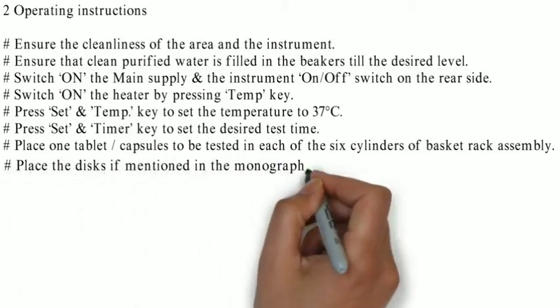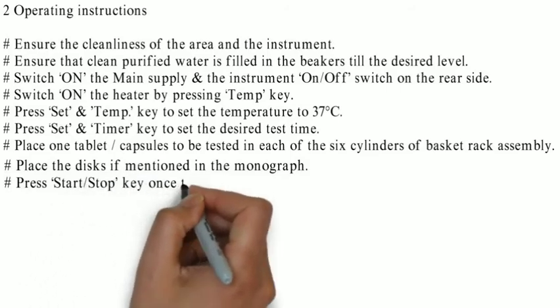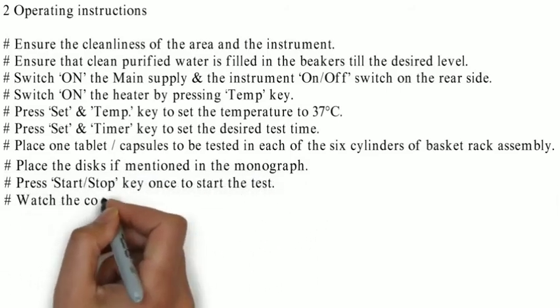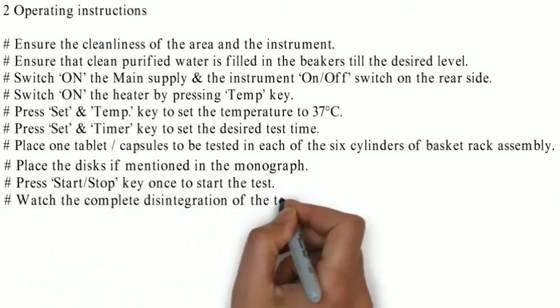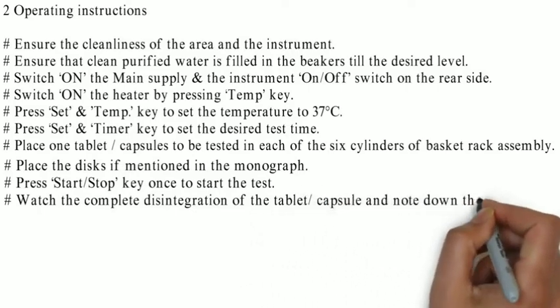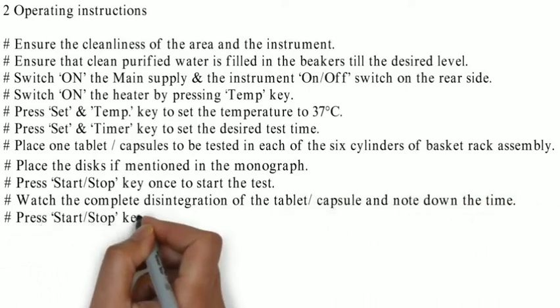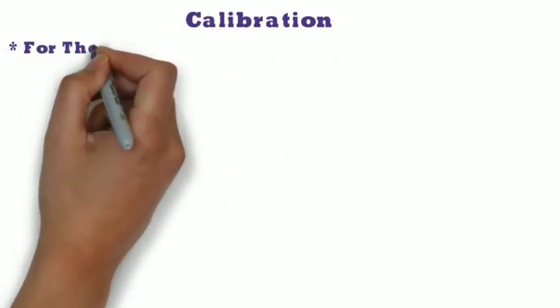Press the start and stop key once to start the test. Watch the complete disintegration of the tablet or capsule and note down the time. Press the start stop key to stop the test. Calibration. For calibration, first we have to check the thermostat.